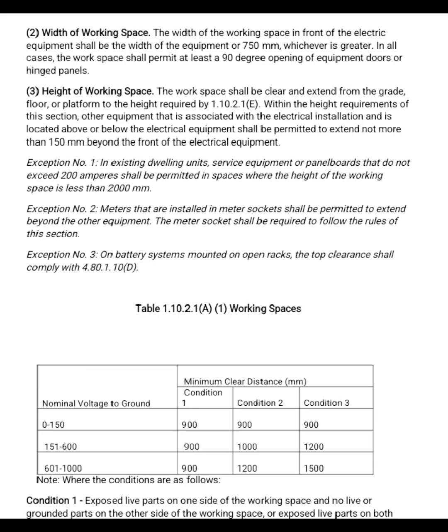Exception number 1. In existing dwelling units, service equipment or panelboards that do not exceed 200 amperes shall be permitted in spaces where the height of the working space is less than 2,000 mm. Exception 2. Meters that are installed in meter sockets shall be permitted to extend beyond the other equipment. The meter socket shall be required to follow the rules of this section. Exception 3. On battery systems mounted on open rack, the top clearance shall comply with 4.80.1.10D.